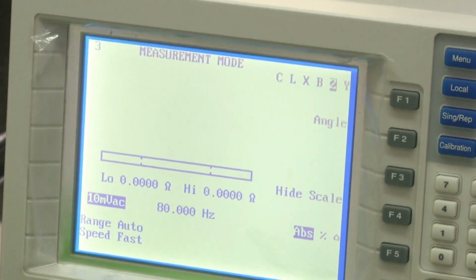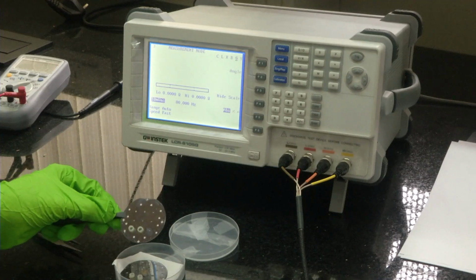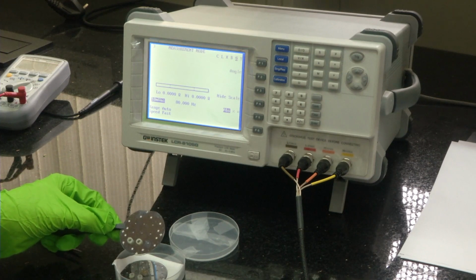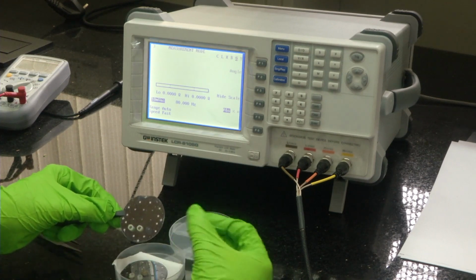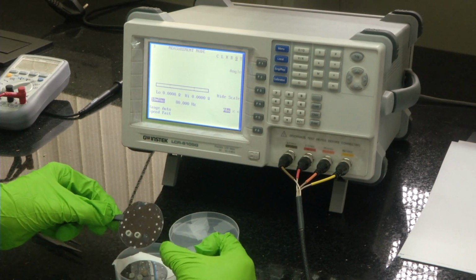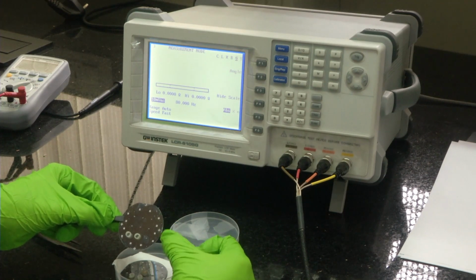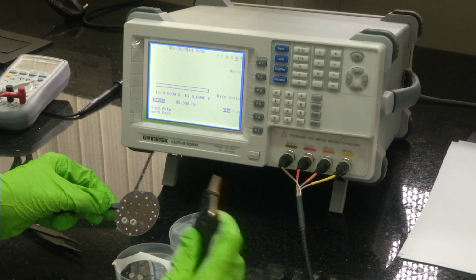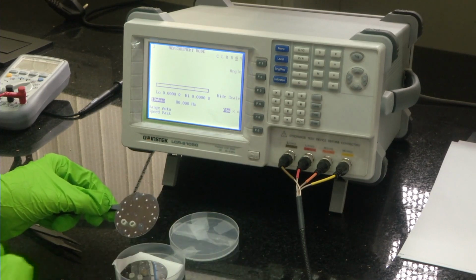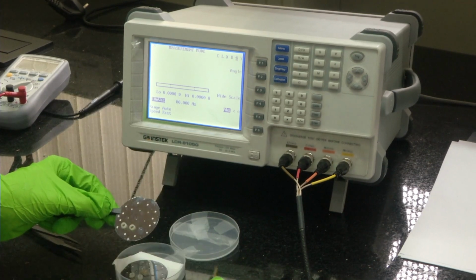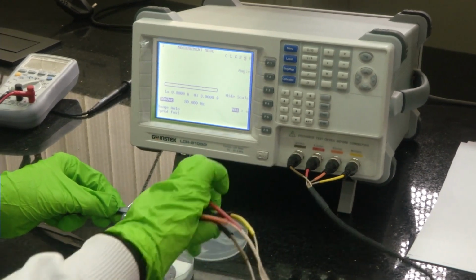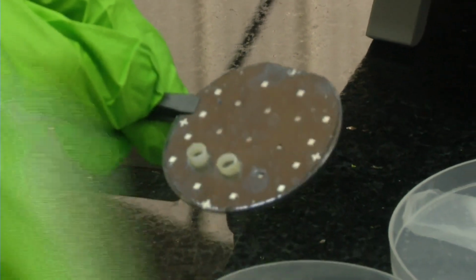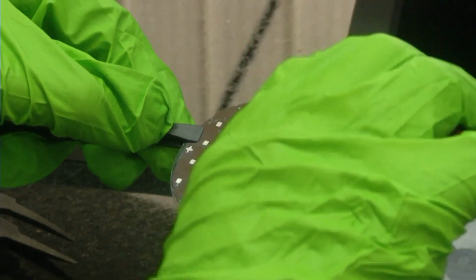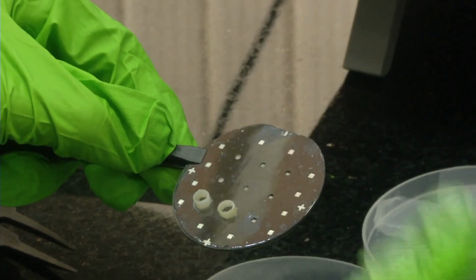Now, let us just have a look at a sensor. This is one sensor that we have in our lab. As you can see, there are contact pads. These 4 squares which you see are contact pads. If we are probing, we have to have a metal probe that will go and touch these. It is not advised to manually take the probe and put it on top of that. For that we have other equipment like micro manipulators and probe stations, which we can use to make the contact, touch these contact pads and actually measure the impedances.